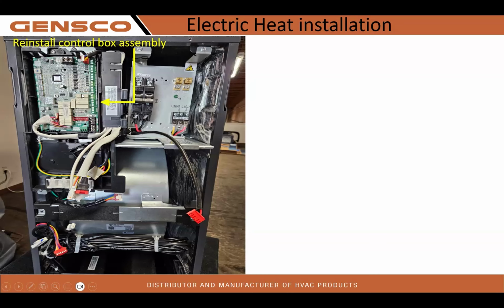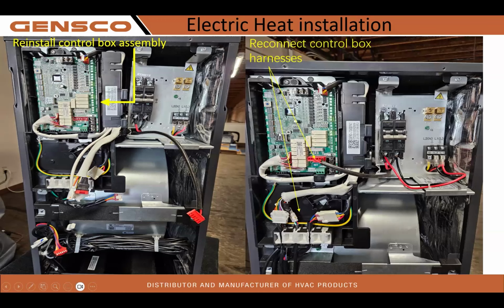Reinstall the control box assembly. 3 screws go back in. Reconnect the control plugs. Remember, they're one-way gated. You can't accidentally mix match any plugs. And notice right here, that plug that I wanted you to cut the end off of is now our jumper that we're going to land on the load side of the breaker that powers our heat kit. And we are merely landing them on line 1, line 2, and ground. So that plug that we're not going to throw away, we just cut the flat plug off, strip it, add it to our breaker, and use those stake-on connectors that are already there to land power that powers our indoor control board.